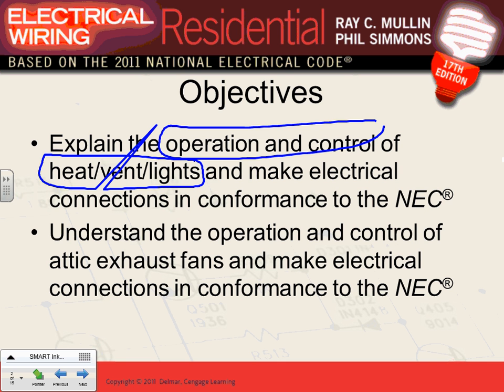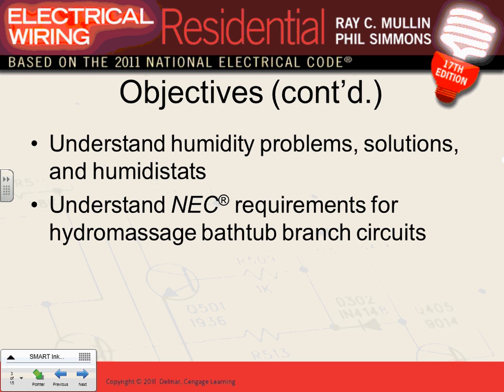Operation and control of exhaust fans. You guys have an exhaust fan in the laundry room. How are you going to operate this? We provided a 20 amp circuit to our exhaust fan in the laundry room. This one in the attic, no difference. And how do you want to operate it though? So provide a 20 amp circuit, right? And then how are you going to operate this equipment? You're going to operate it based on temperature. You're going to have so many ways of controlling it. When the temperature rises to a certain limit, basically temperature control, it starts, thermostat. So there are a bunch of other ways we'll talk about, because the last thing you want to do is just turn it on and off yourself. So we'll talk about the exhaust fan control.